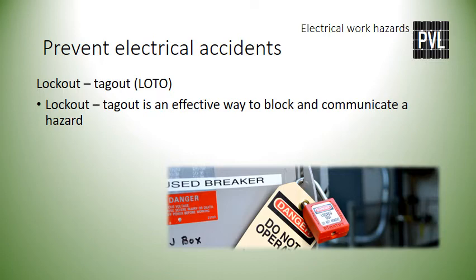A tagout is when a durable tag is securely attached to the switch to warn others not to energize a particular switch or circuit breaker. Generally, the tag must also contain your name, photograph, worker identification number, and telephone number. Your information on these lockout/tagout devices is important so you can be contacted if you forget to unlock the switch or circuit breaker when done, or if someone needs more information. Often, locks and tags are used together — thus called lockout/tagout, or LOTO.